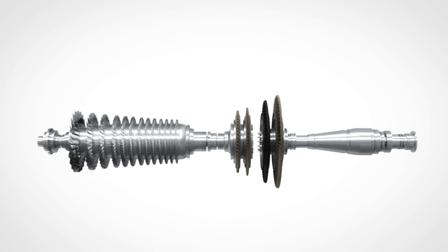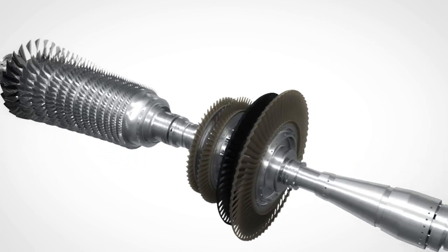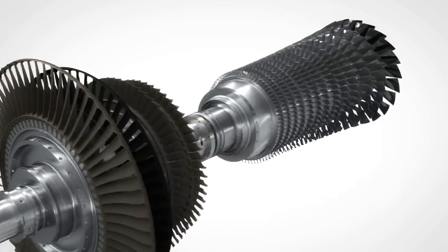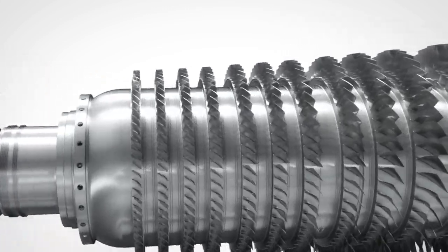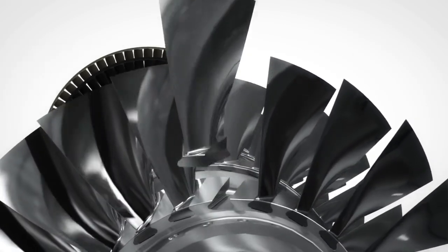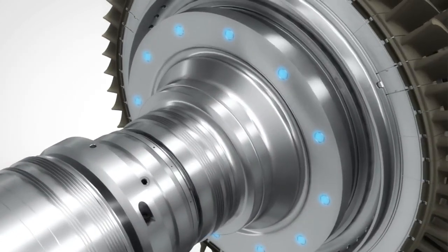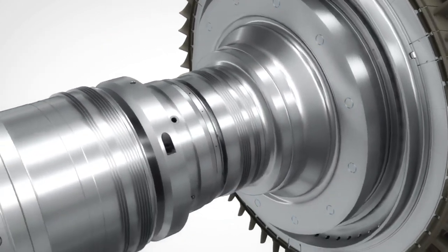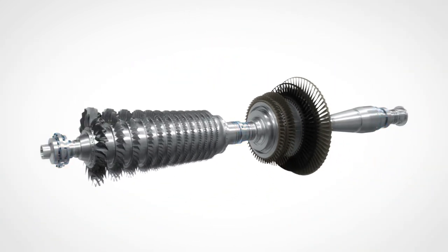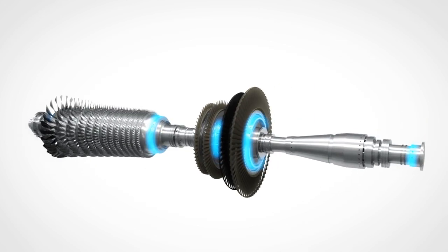The rotors incorporate the heritage of Siemens electron beam welding. The single rigid compressor rotor body ensures reliable, stable and uniform run up in hot or cold conditions. Axial blade attachment grooves allow blade replacement without rotor removal. The turbine discs are bolted to the compressor rotor and supported with mineral oil lubricated long life tilting pad bearings. The balancing planes allow field balancing on site without disassembly.